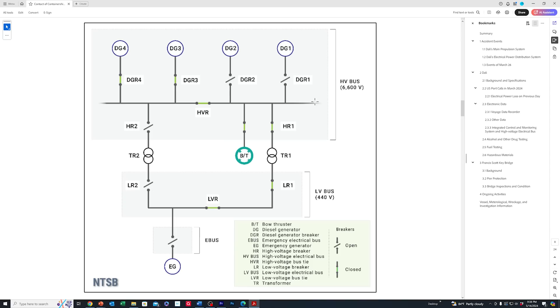What the crew did next was close the breakers HR1 and LR1, reconnecting generators 3 and 4, restoring electrical power to the low voltage bus and supplying power again to the entire vessel. They reclosed the breaker that had popped open, LR1, and then HR1, allowing the 6600 volt bus to go through the transformer to the 440 volt bus and get everything going.